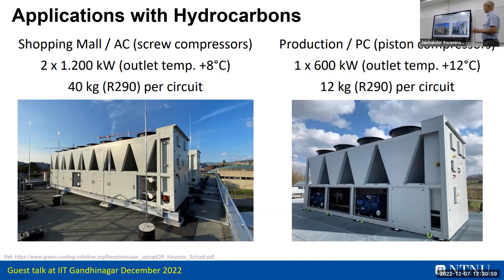Even inside, you can have smaller units. Each unit has 2 kilo of charge, and the likelihood that all of them leak at the same time is zero. So it can be treated like this: you treat only the one with the maximum charge as the one corresponding for the room. It depends a little bit, but it's all in the standard. If you follow the standard, you can do this safe, and you have to follow the same standard if you use F-gases which are flammable. So there's no difference, kind of, from the restrictions.